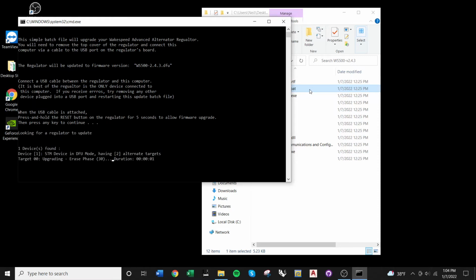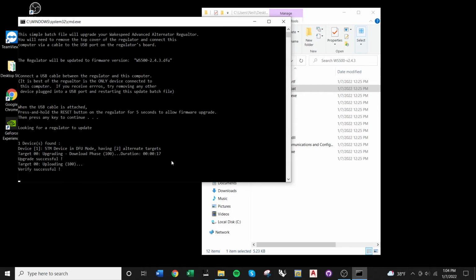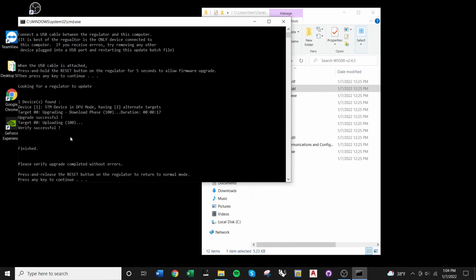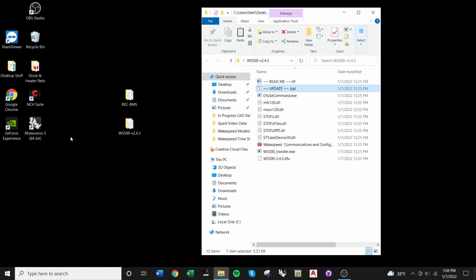You can see here again, we just erased the old firmware, and we're downloading our new firmware. Upgrade successful. We're going to hit the reset button on the regulator to return it to its normal mode, and then press any key to continue. And that closes us out, so we have our firmware loaded into our regulator.